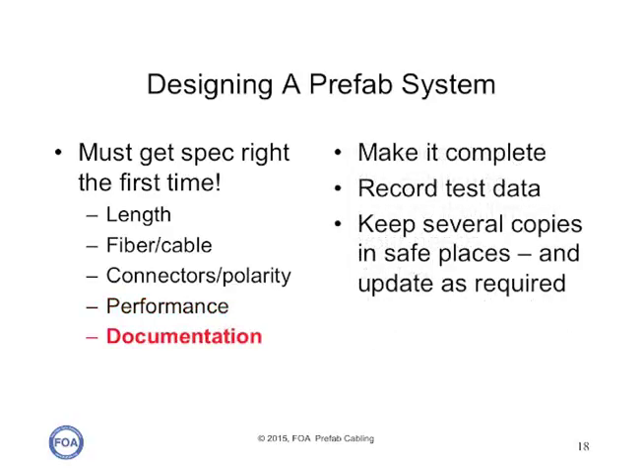The documentation on your design and on the cable plant as built must be complete. You need to record all test data. The manufacturer should have all their test data included in the documentation. You need to keep several copies of the documentation in safe places, because if you do moves, adds, and changes, or have to do any modifications or restoration to the cable plant in the future, the documentation will be a lifesaver.